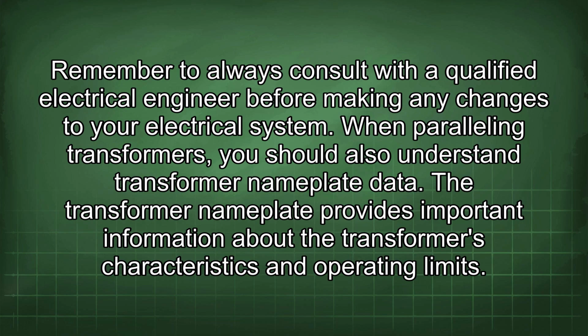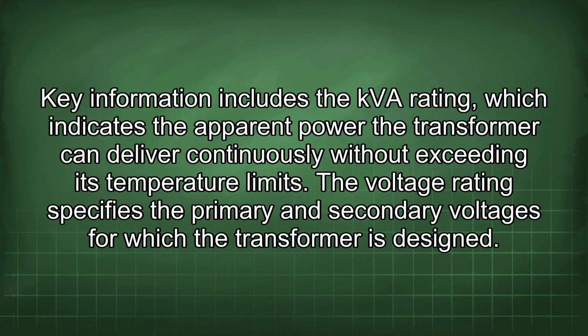When paralleling transformers, you should also understand transformer nameplate data. The transformer nameplate provides important information about the transformer's characteristics and operating limits. Key information includes the kVA rating, which indicates the apparent power the transformer can deliver continuously without exceeding its temperature limits. The voltage rating specifies the primary and secondary voltages for which the transformer is designed.